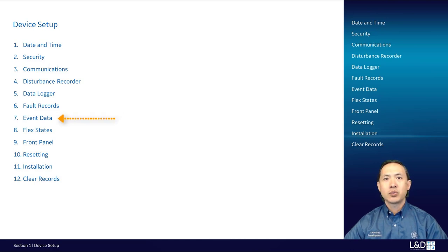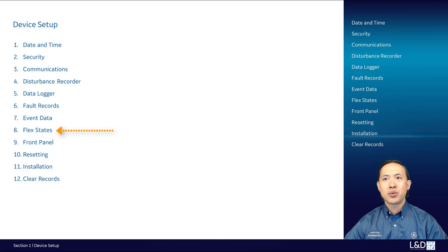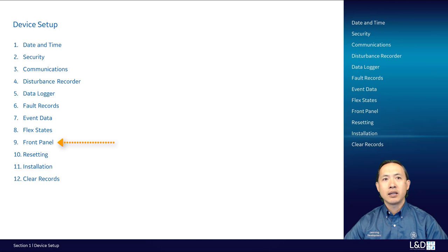The relay is able to capture a maximum of 2048 event records. For each event record, the event data feature stores up to 64 flex analog quantities each time an event occurs. The FlexState feature provides a mechanism where any 256 selected flex logic operand states are saved into 16 Modbus registers starting from a designated address. On the front panel, we'll introduce the programmable LEDs 5 to 8, display properties, and display time under the default screen.